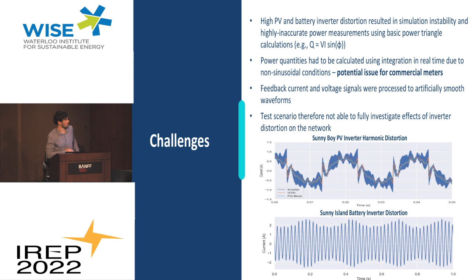But this also has other ramifications, because for this peer-to-peer scheme to be feasible, and for the exported power to match the amount agreed in the market to a close degree of accuracy, you'd have to use this real-time integration technique. If you just use a traditional approach assuming a perfect sinusoidal wave with power triangle equations, you get results that aren't particularly close to what was traded in the market. This is a potential issue for existing commercial meters, since many assume a perfect sinusoidal wave, which isn't always true - especially with these commercial inverters currently flooding the market, particularly in Australia. So we need to do more work on what kind of ramifications this will have for these markets to be successful in the future.